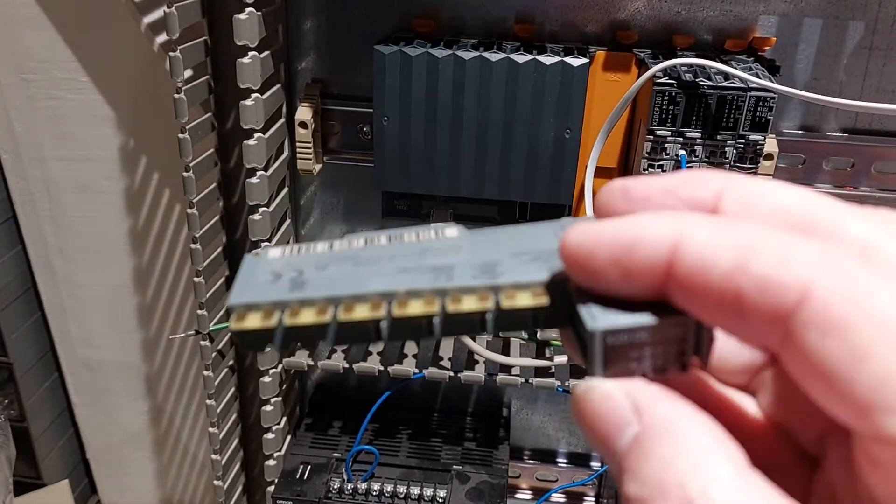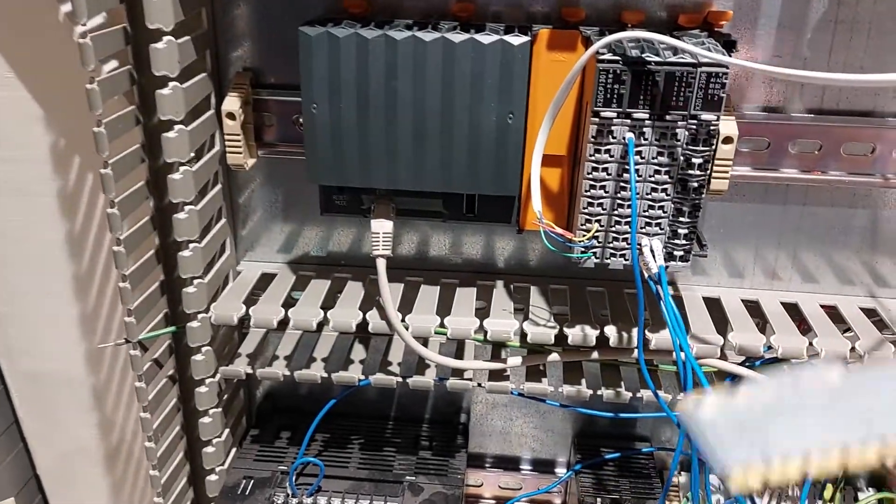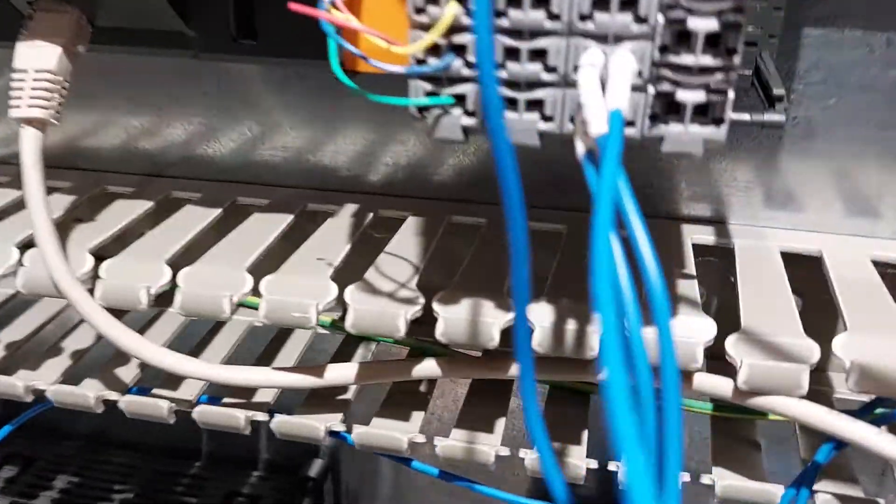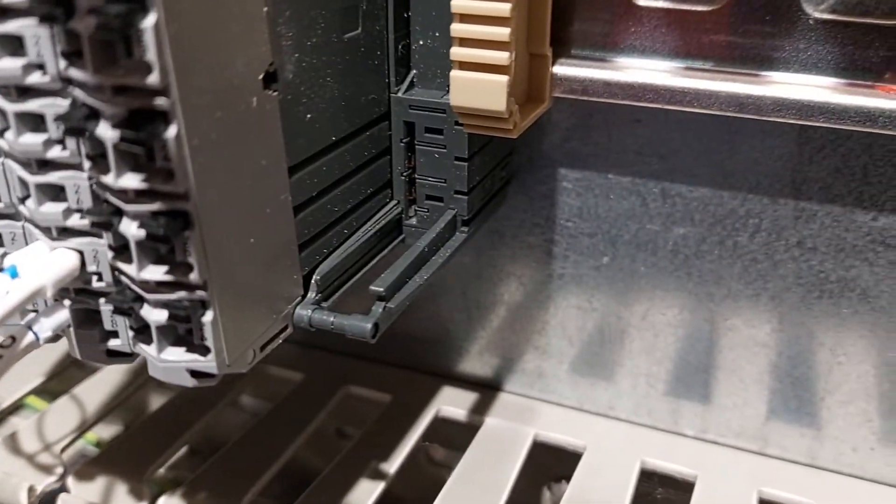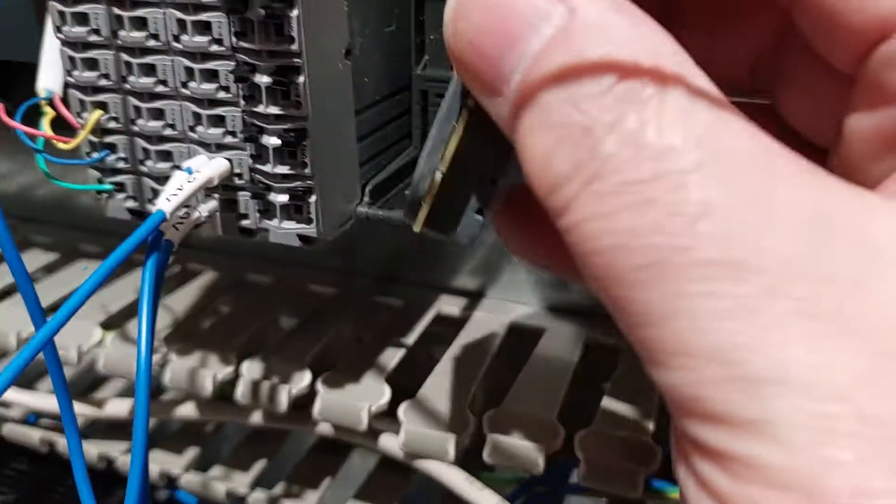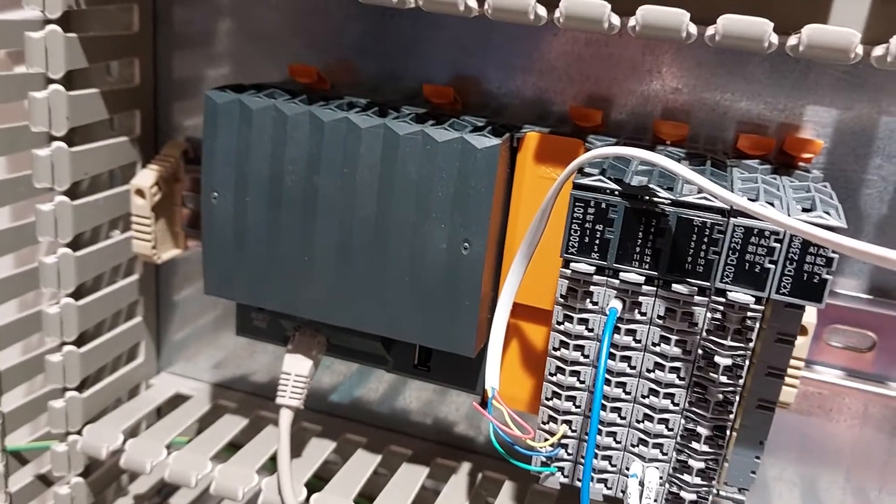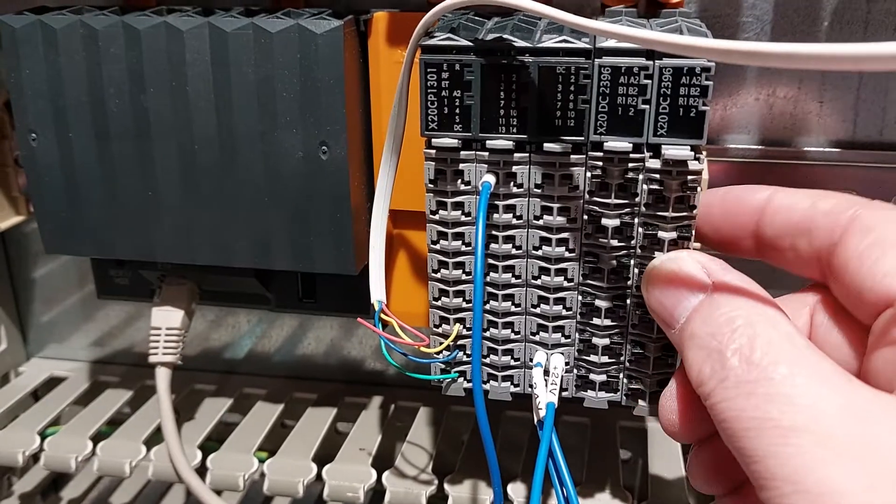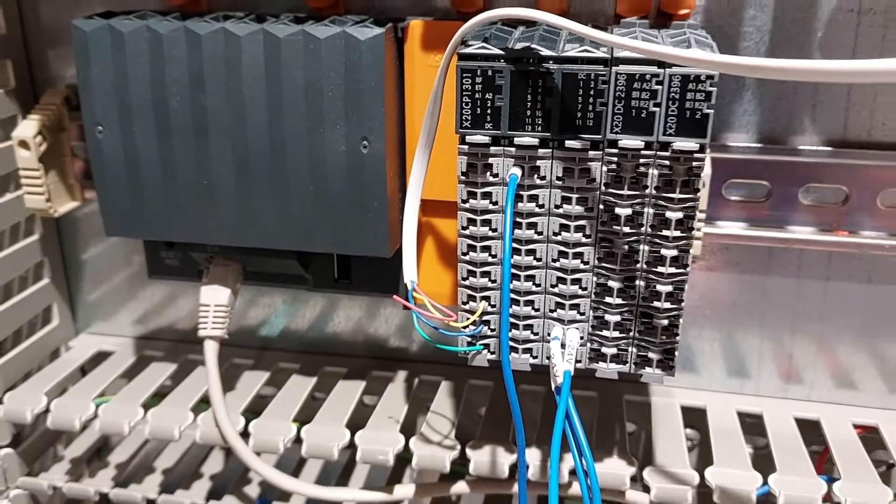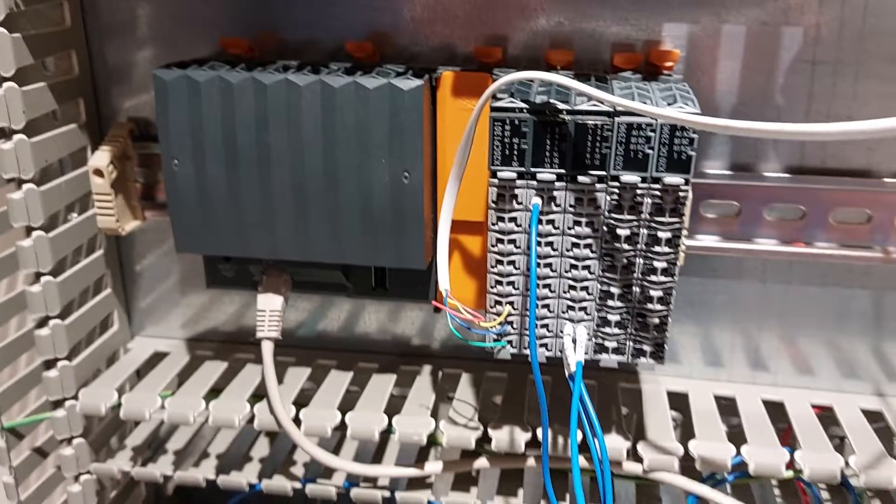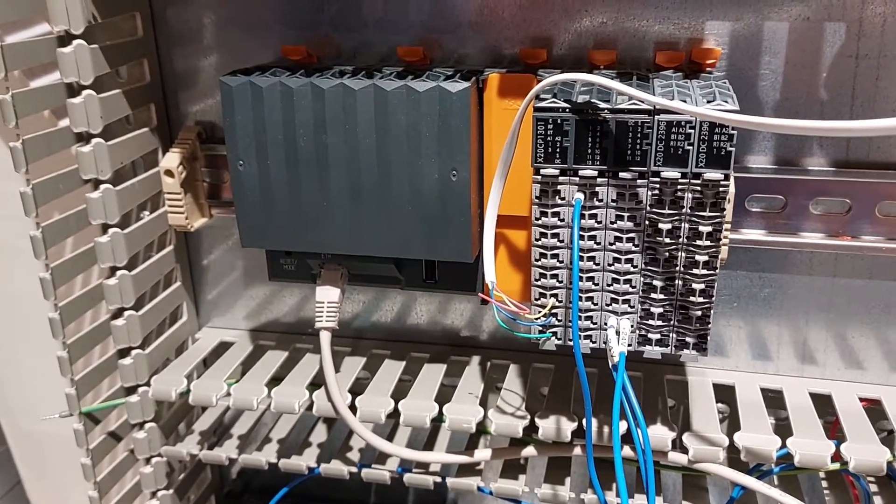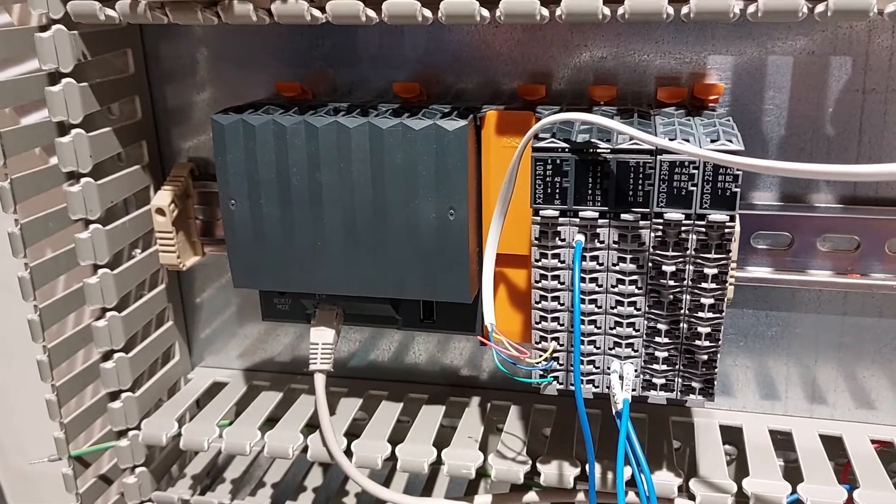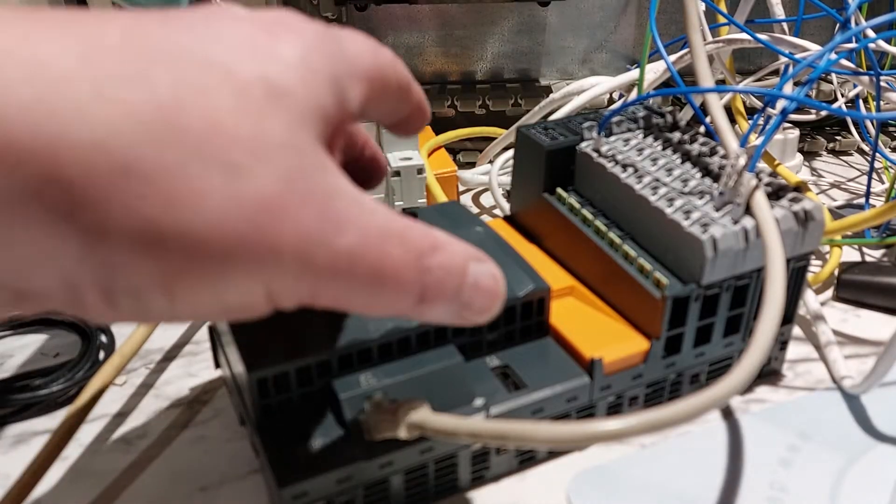So if you're replacing a module, this is the bit that you will get in the box, and that's the bit that you need to slot back in. It does have some runners in the bottom, some grooves that you need to get it in there. You can see the groove there and that is to fit inside the groove. Push it back, slot it in, and then get the connector with the wires and just flip it back in. And that is how you actually replace a module. If you need to actually try and make sure the connection across the PLC modules is all good, they're all properly inserted, I'll show you in just a second.